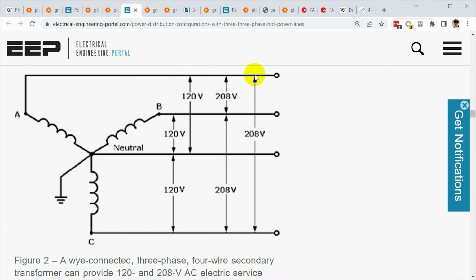Well, why is it done that way? Why isn't it 240? Well, it's done as 208 because that makes each one of these phases 120 volts. And that is very convenient when you have a building where you're going to have three-phase high power loads, but you also are going to have lights and outlets, and you need 120 volt circuits as well. This allows you to wire up your 120 volt breakers across a single phase to neutral, and you have that 120 volts in the panel. But if you put in a triple breaker and tap all three phases, you have your 208 volt three phase.